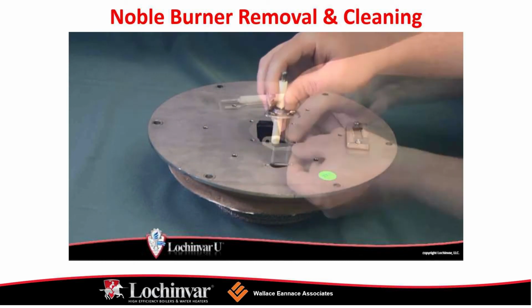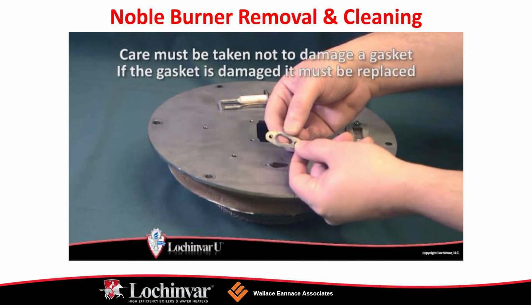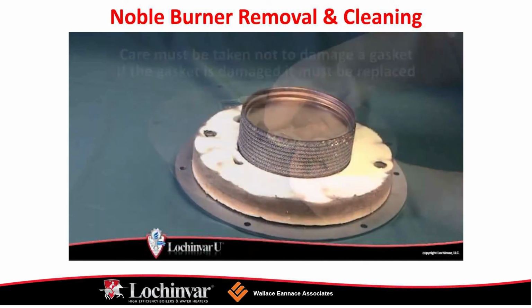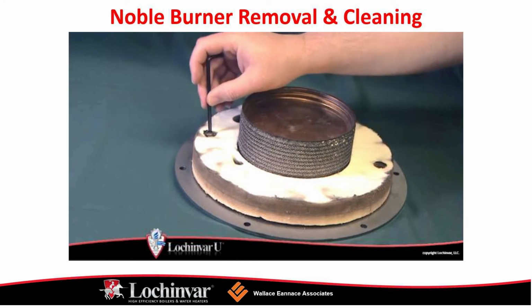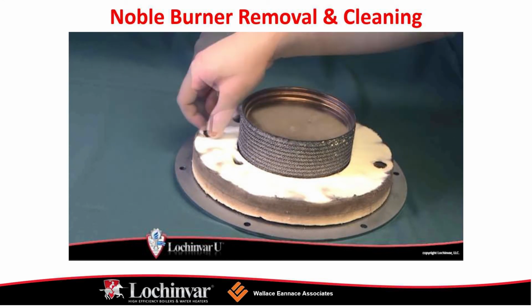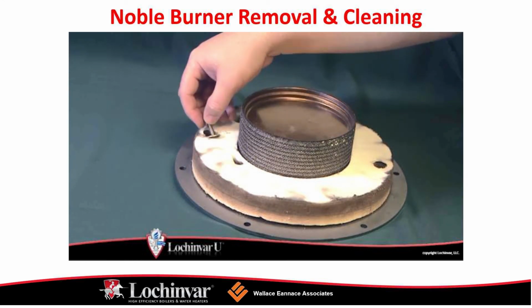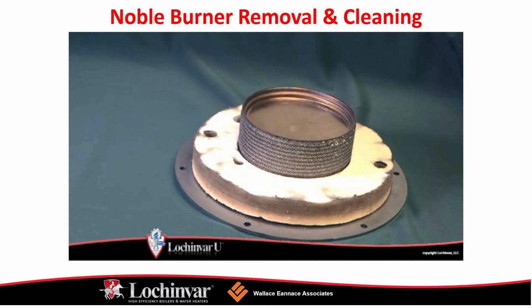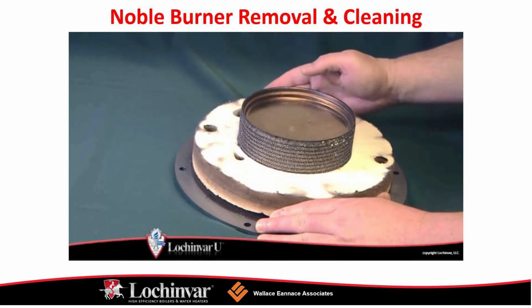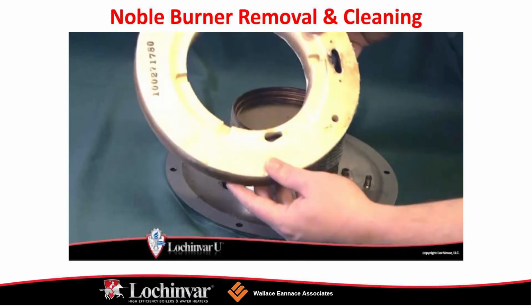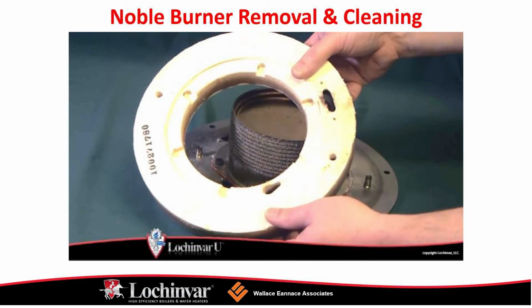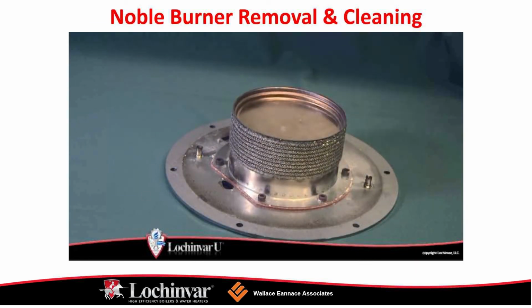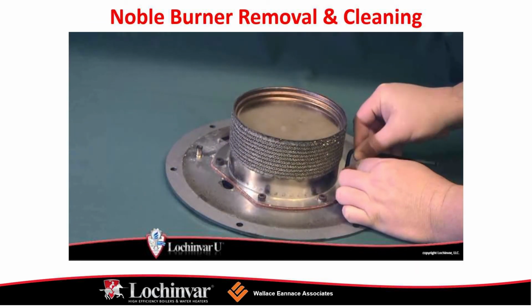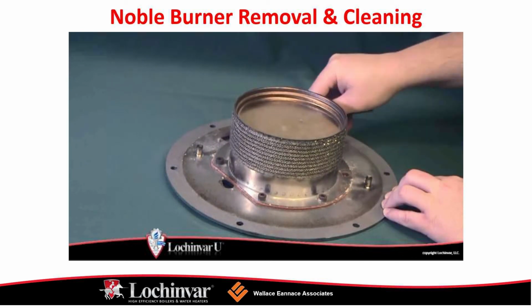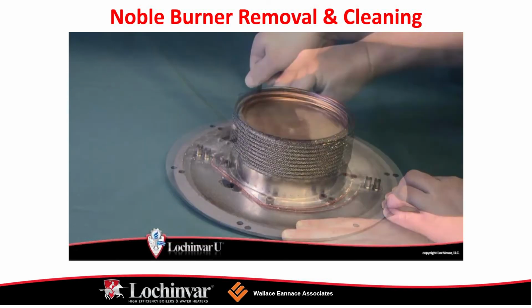Using a 5/16" nut driver, loosen the ratchet clamp that secures the air intake piping to the Venturi assembly. Then, using a 5/16" wrench or socket, remove the 4 screws that secure the fan assembly to the heat exchanger top plate. Now remove the fan assembly and Venturi from the unit. A gasket is used to seal between the fan assembly and the heat exchanger top plate. Care must be taken not to tear or damage a gasket. If a gasket is damaged or torn, it must be replaced.